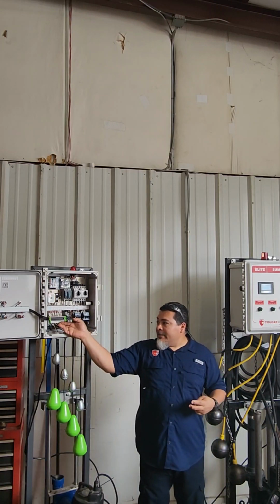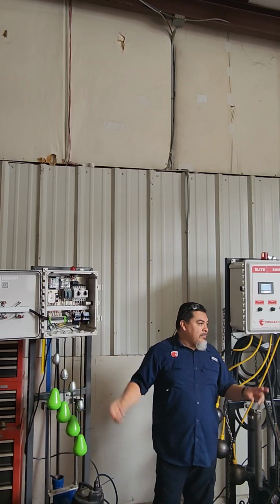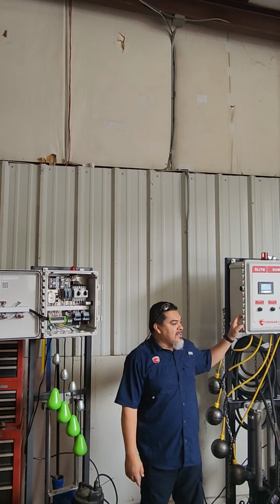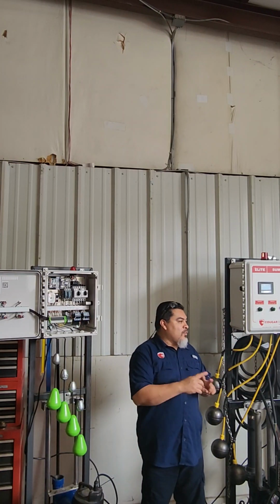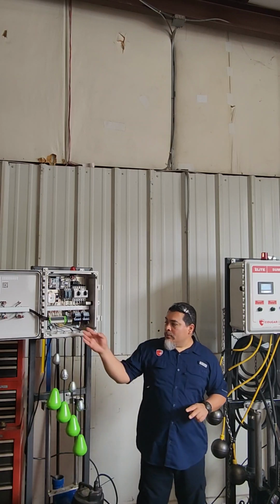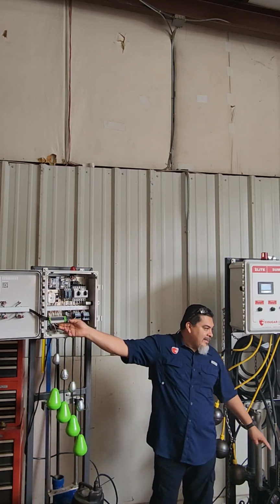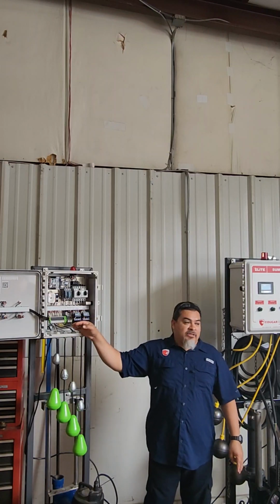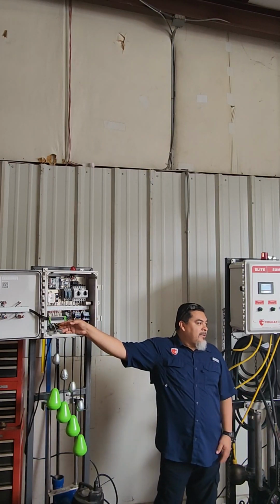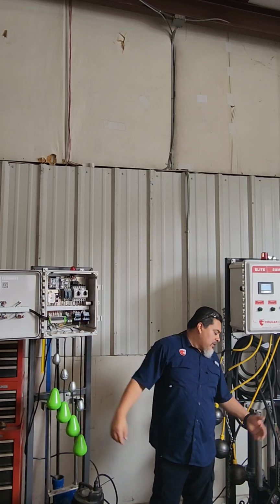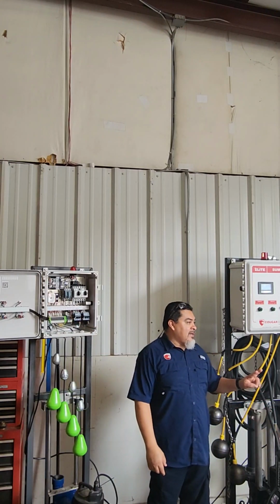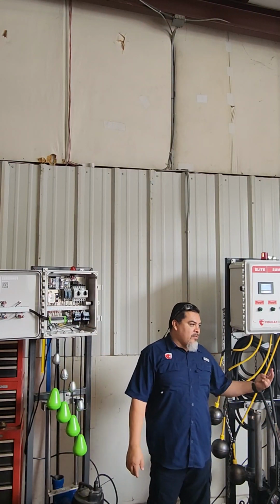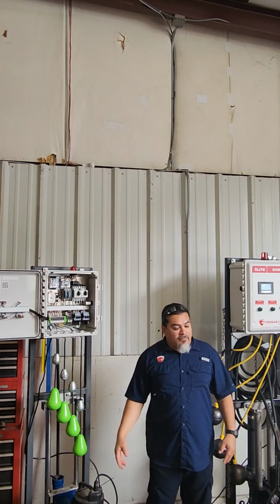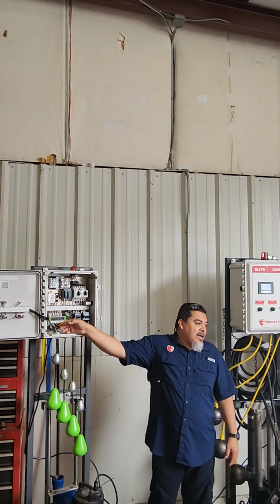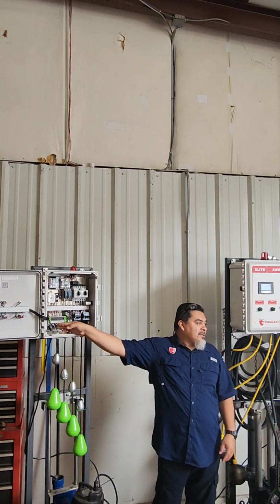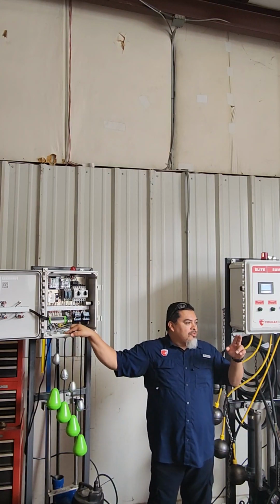So on your high temp connections, it's pretty much tying your neutral to the contactor. So if that's open, you're not sending 120 to the contactor. So we put jumpers if there's no high temps, because I do get a lot of those. Hey, we just installed a panel, but the pump doesn't come on at all. Or you replace the pump and the pump doesn't have high temps. There are different pumps. Some come with high temps, some don't. So if it doesn't, all you gotta do is remove that existing cable and put a jumper to it to bypass. So that will close that neutral.